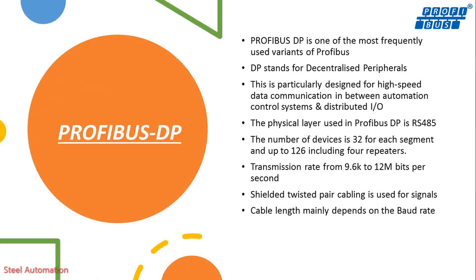Profibus DP is one of the most frequently used variants of Profibus. DP stands for Decentralized Peripherals. It is particularly designed for high-speed data communication between automation control systems and distributed I/O. The physical layer used in Profibus DP is RS-485.